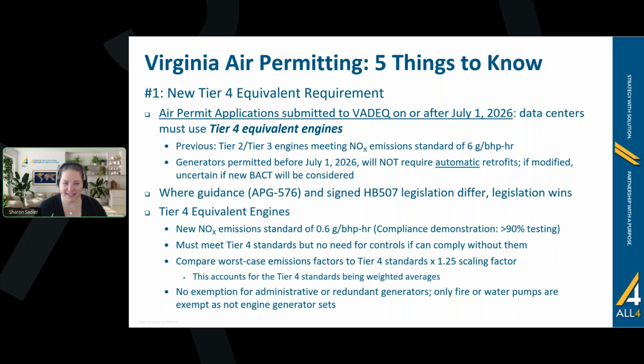Now, a question that people raised: you heard when I went through the control devices, I said you may need an oxidation catalyst, may need a diesel particulate filter. The reason is that even though the guidance read as though you had to have the control technology, because the legislation just says Tier 4 equivalent, the need to have controls is only if you actually need them. For example, carbon monoxide is a pollutant where, even looking at that emissions data from the vendor, the not-to-exceed potential site variation worst case data, if those numbers are less than the Tier 4 standard and you can comply without an oxidation catalyst, then you don't need to put one on.